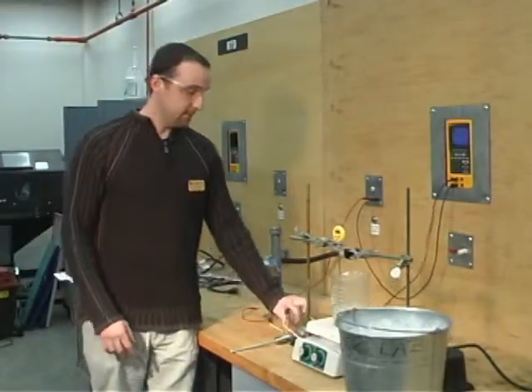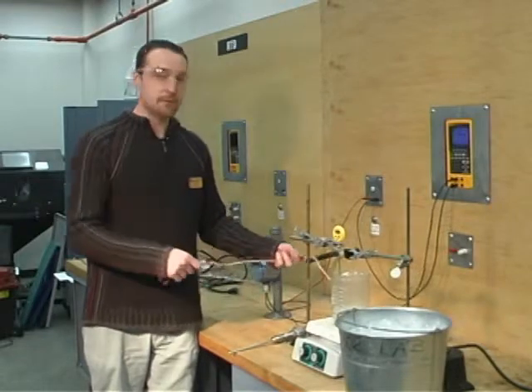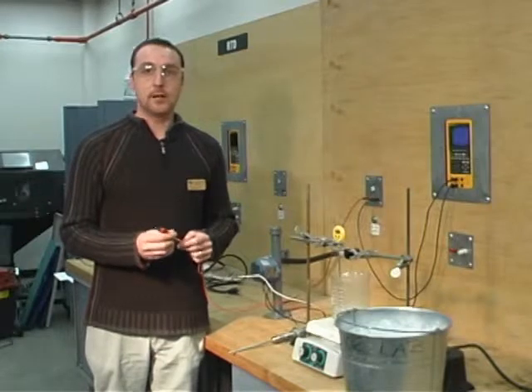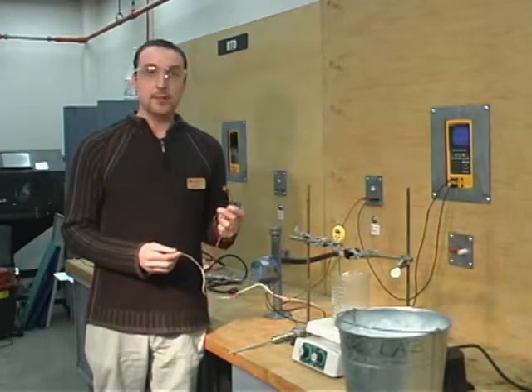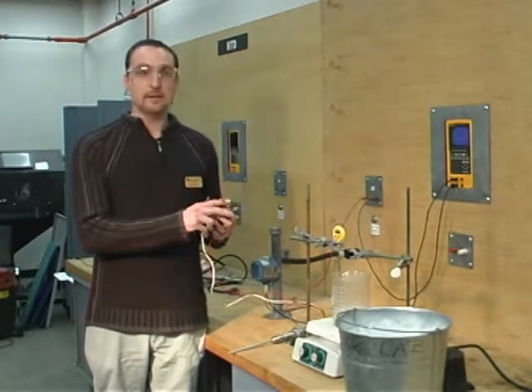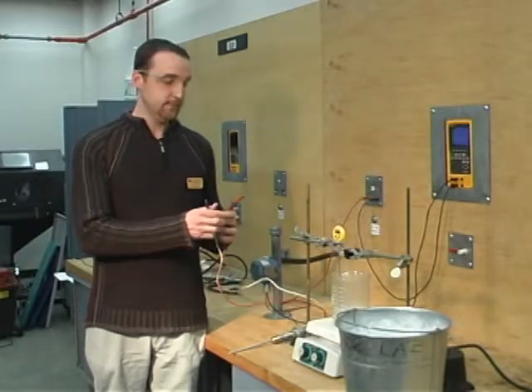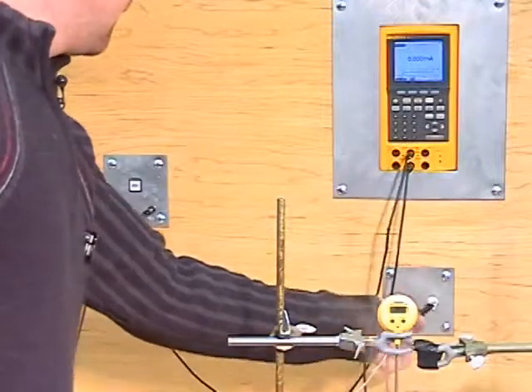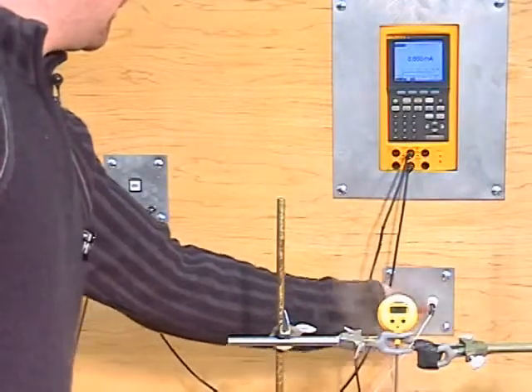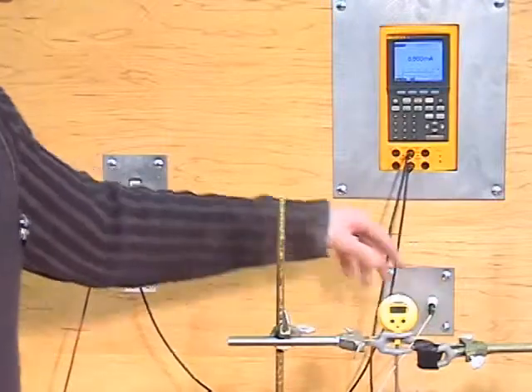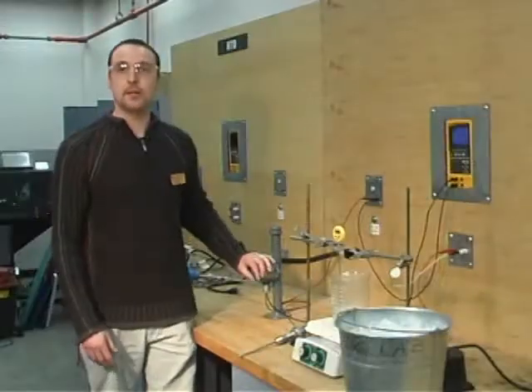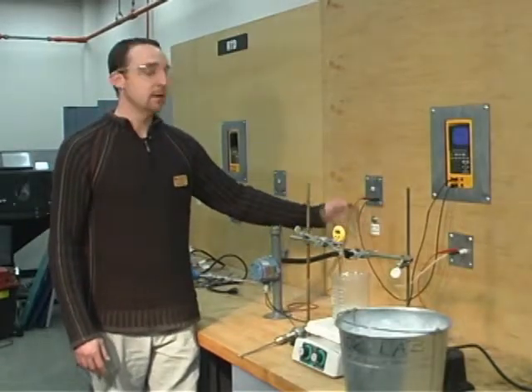Now next step, we will connect our J-type thermocouple. Also note, with a J-type thermocouple with North American color code standards, the red sheathing on the wire is actually the negative wire. So we will plug our thermocouple to these Pomona jacks. Through these Pomona jacks, it is wired directly internally to the transmitter. Now since our transmitter is connected properly here in a series loop, we can apply power to it.